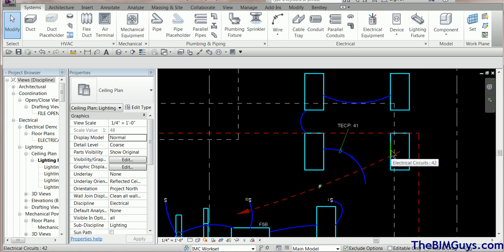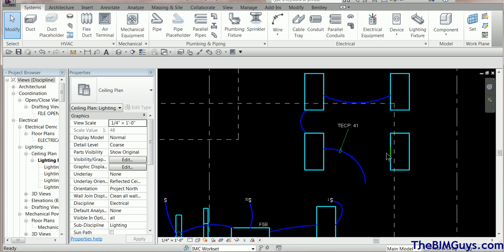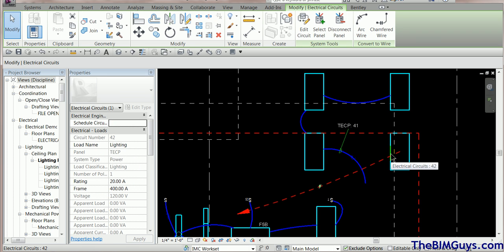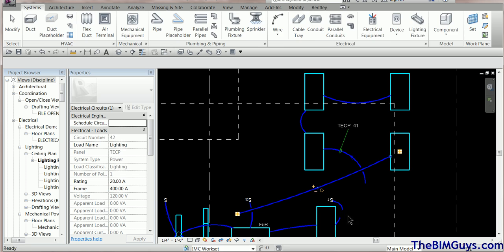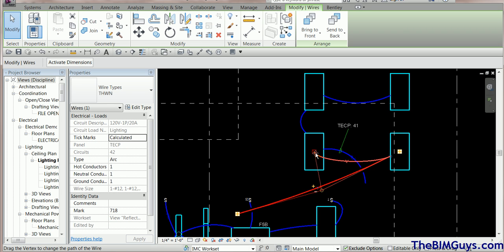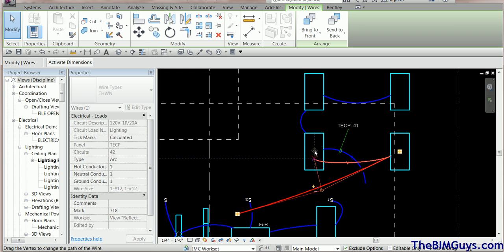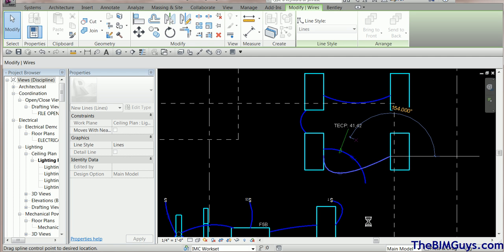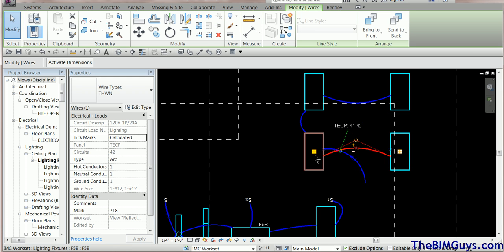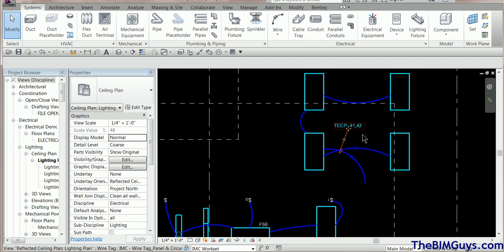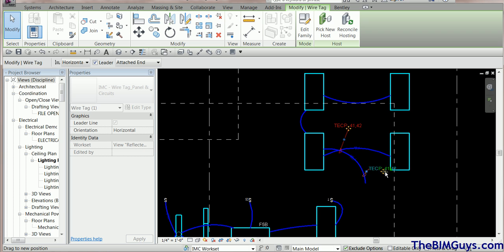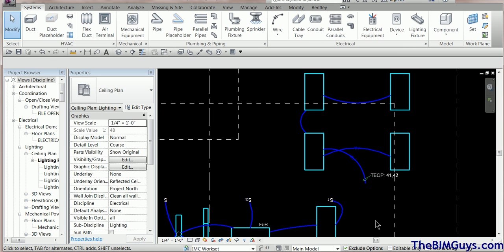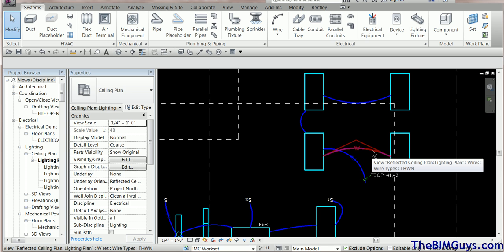It wants a home run because it's only a single element. The trick is the Tab key — hold over the element, hit Tab repeatedly, and see how it cycles through different selections. When it highlights the circuit, you can tell it to wire, creating a separate home run. But if you want to run them together, drag the wire endpoint to the center of the other fixture — when you land on the connector, it reroutes the home run back through that fixture.